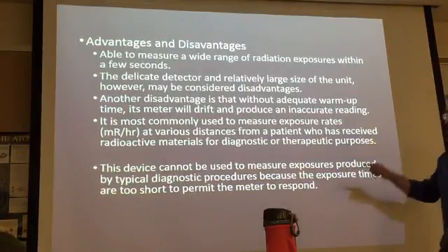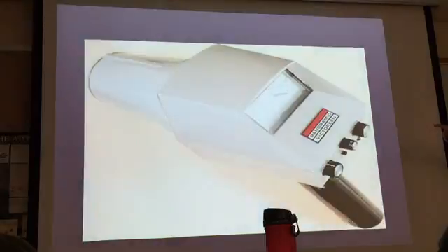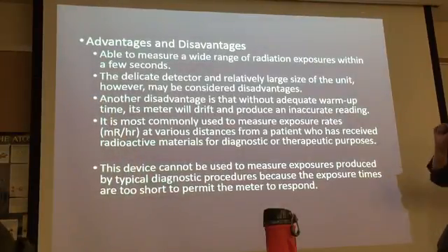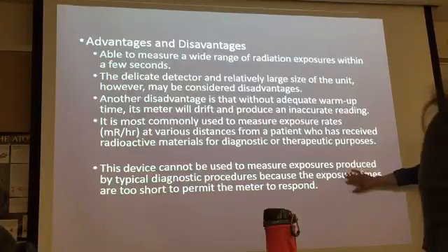This device cannot be used to measure exposure produced by typical diagnostic procedures because the exposure times are too short to permit the meter to respond. And I'm talking specifically about the cutie pie. So make yourself a note and say, this refers to the cutie pie. You're not going to get that device and put it next to an X-ray tube. It's not going to work. It's not sensitive enough. Make sense? So this is specific to the cutie pie.